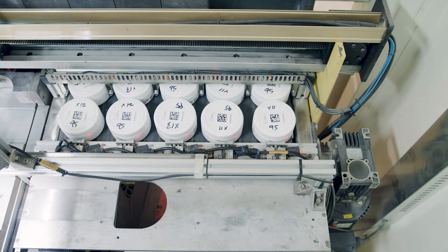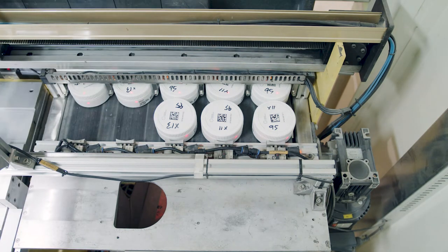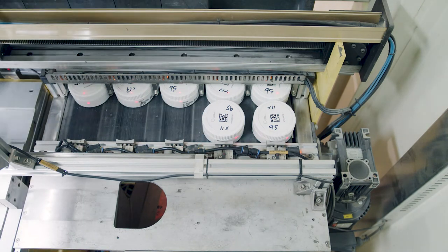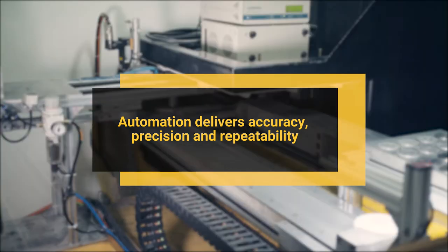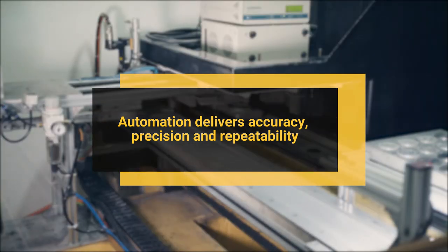The automated sample handling system is a robotic unit designed to automatically receive samples, present them in turn to the X-ray source and detector systems, and eject samples from the photon assay system once analysis is complete.